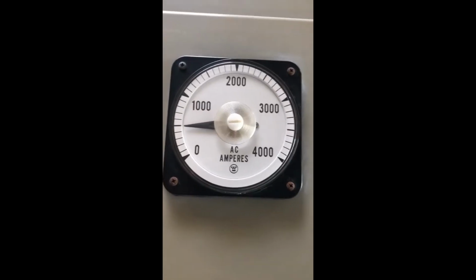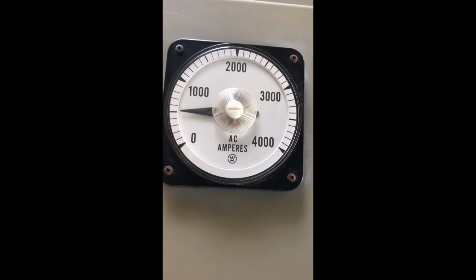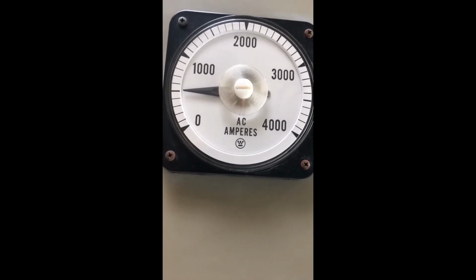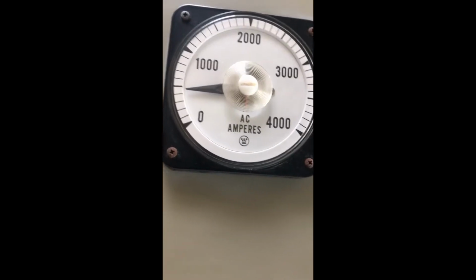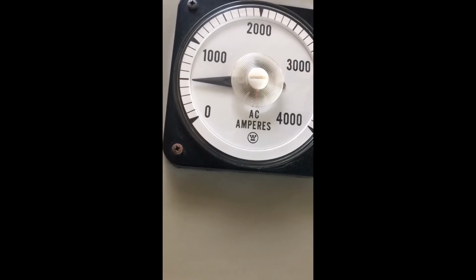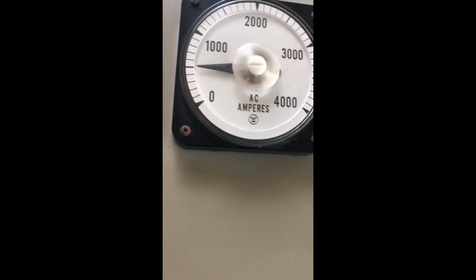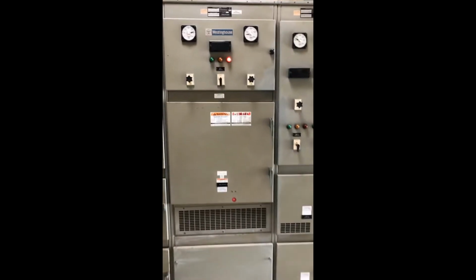Well, let's just check it out. So I got 500 amps on A phase. Moved up a little bit on B. Yeah, it looks good. The whole idea is that the load should be balanced across all three phases. So power looks good coming into the plant, and then from the main breaker, that powers the bus bar going across this switch here.